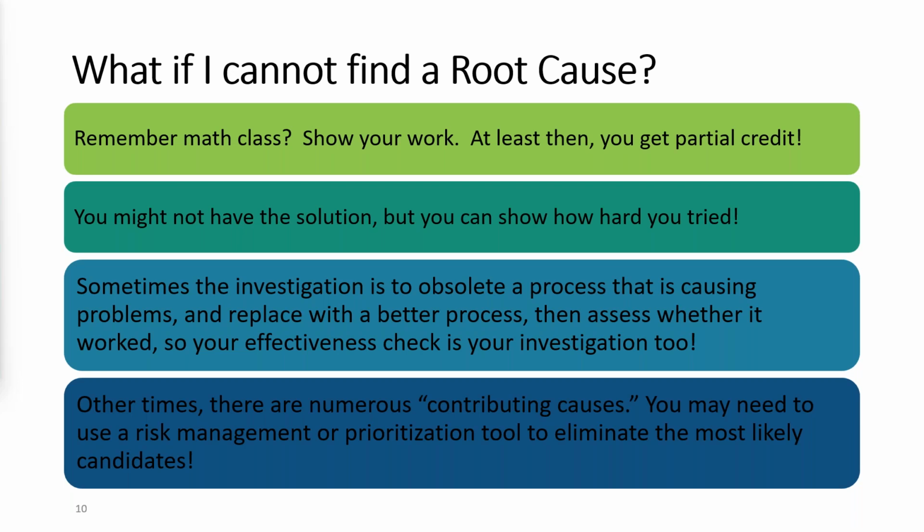But it would be very difficult to justify to the FDA that you are extending a CAPA simply because you didn't have sufficient resources to resolve it. The FDA does expect that an organization be adequately resourced to take care of CAPA. So there had better be documentation that says you had been doing some work and ran up against a roadblock that forced you to be delayed in such a situation.